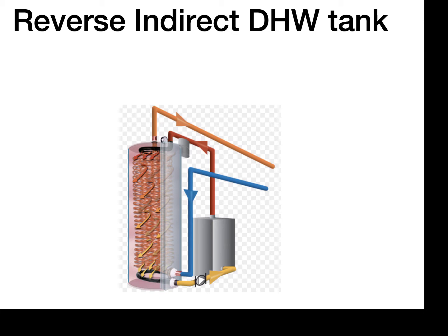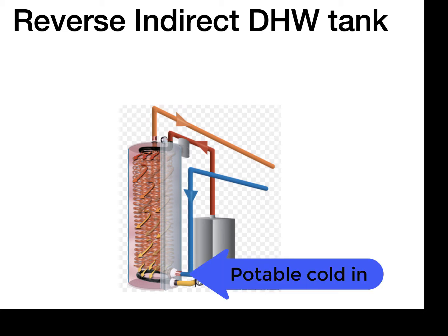Depicted is a cutaway of a reverse indirect type of domestic hot water storage tank. The system does require a heat source, a hydronic heat source. It could be either a ground source heat pump or a hydronic boiler. The major difference between this and an indirect storage tank is the amount of surface for the heat exchange process itself. In this case, you run water through the tank from the boiler or the heat source, and then you run your potable water through the copper coils that are shown on the inside of the tank.